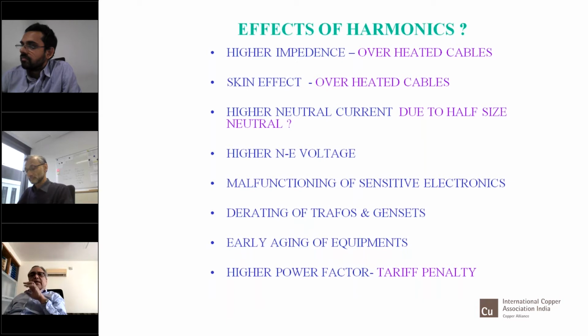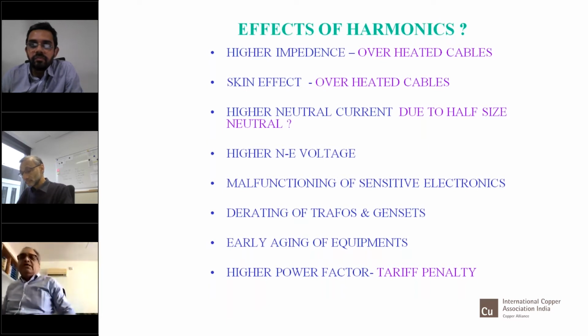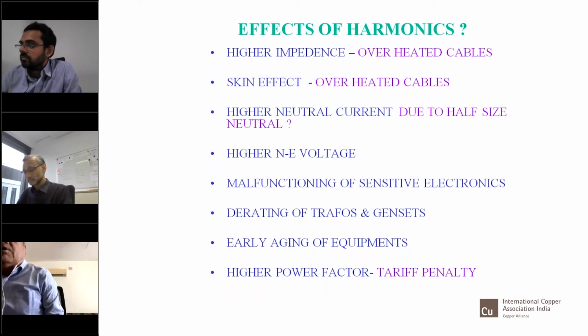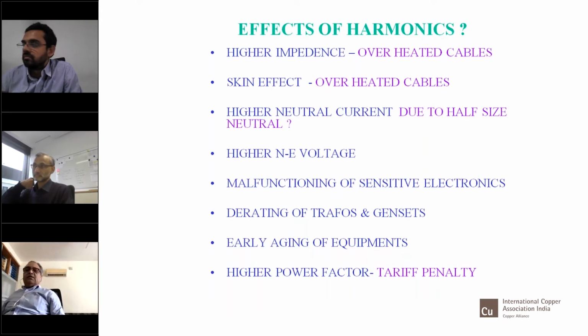And he showed me that the entire cables had some kind of blisters on the surface insulation. Entire insulation was blistered everywhere. Of course I wasn't so aware at that time, so I told him it's due to heating. But later on when I was studying these harmonics, I realized that the entire cable had got burned due to skin effect. On the outer side of the cable the heat was more and the entire insulation had blistered. So these kind of things can happen.